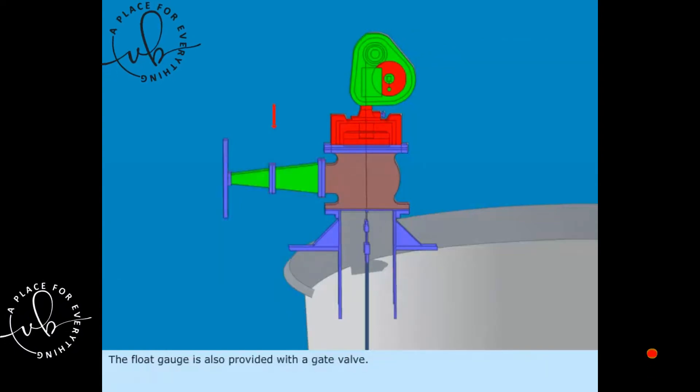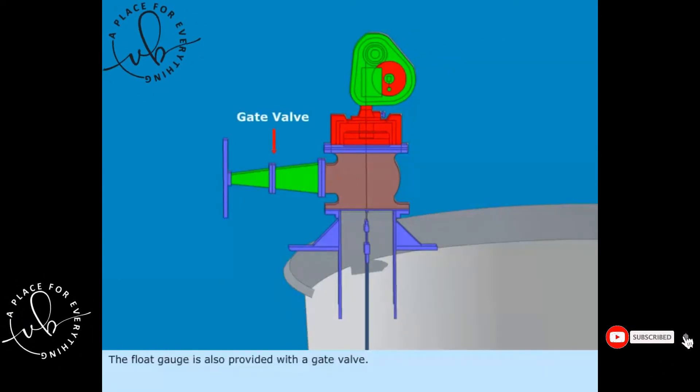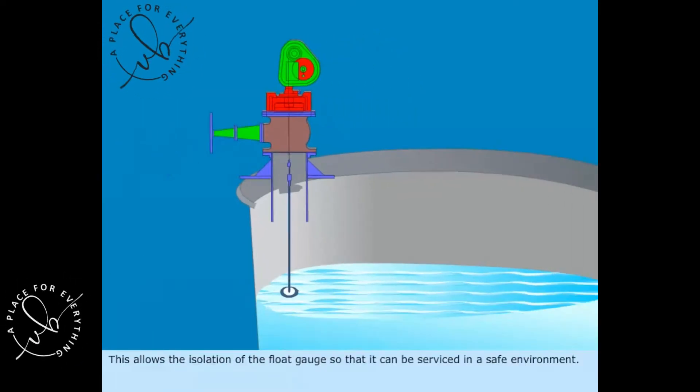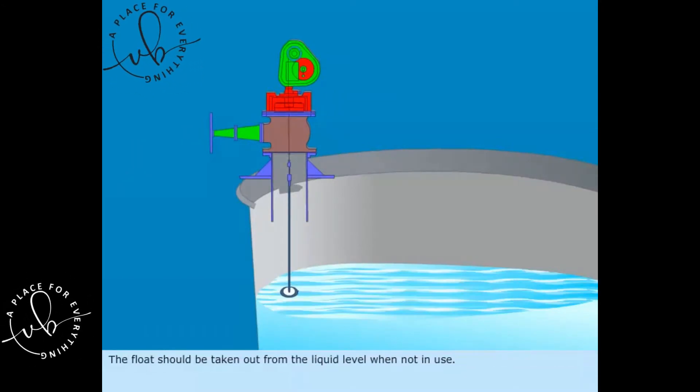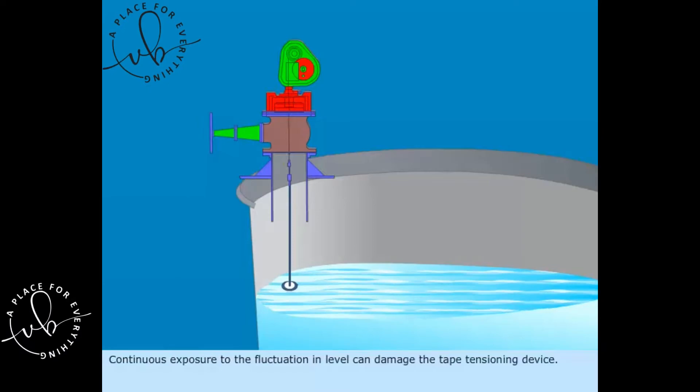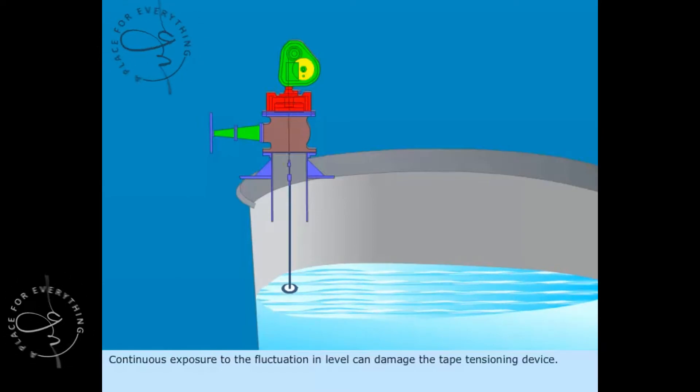The float gauge is also provided with a gate valve. This allows the isolation of the float gauge so that it can be serviced in a safe environment. The float should be taken out from the liquid level when not in use. Continuous exposure to the fluctuation in level can damage the tape tensioning device.